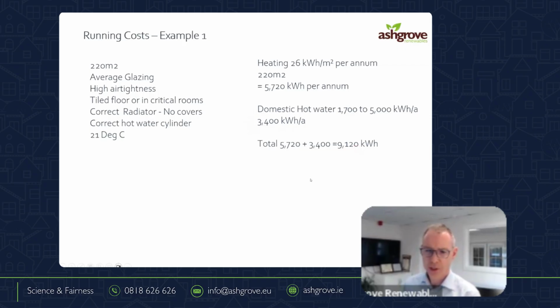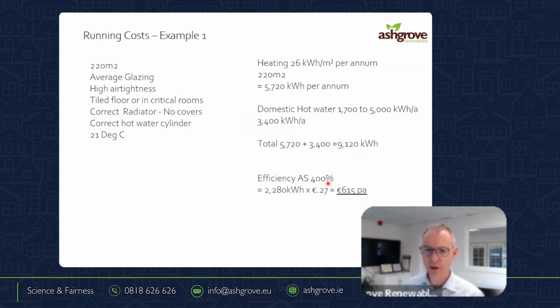I'm going to divide that by, in this case, an air source efficiency of 400%. So the ratio of 4 to 1 that we saw earlier. So I need to buy from the electricity grid 2,280 kilowatt hours, and I'm paying 27 cents for those. That's a total of €615. Now, we might be up or down there by 10%, right? If you use a lot more hot water, that goes up. But it can't be at €900, it can't be €1,000.